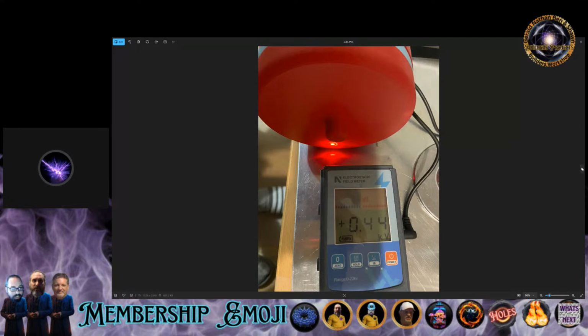Now look at this, my meter is on the metal. The meter has its own ground, so it's connected to the metal, and then house ground is connected to this plate, and voila, now your meter doesn't drive you crazy. If you don't have this specific setup—if you start moving your meter around to places, like throwing it on a bench with a black silicone cover or a wooden desk, and try to measure this—nope, it's going to give you conflicting readings. It's going to cause you to go crazy. You have to get that neutral area, that balanced area, and then you can start reading fields.